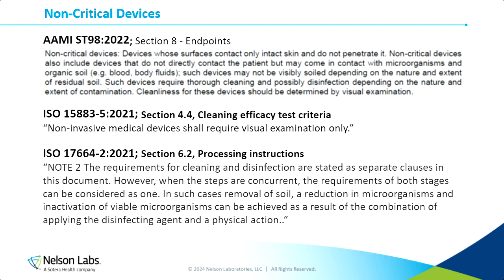And then in ISO 17664-2, which relates to non-critical devices, there's something we wanted to bring up. It states under note 2, the requirements for cleaning and disinfection are stated as separate clauses in the document. However, if the steps are concurrent, the requirements of both stages can be considered as one.